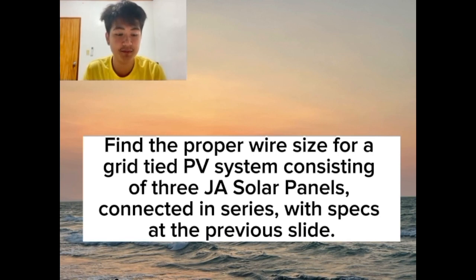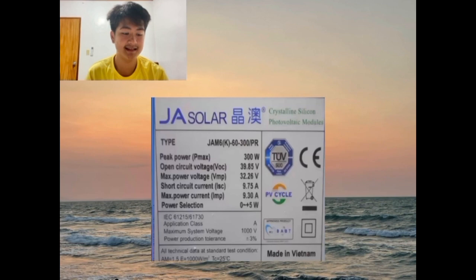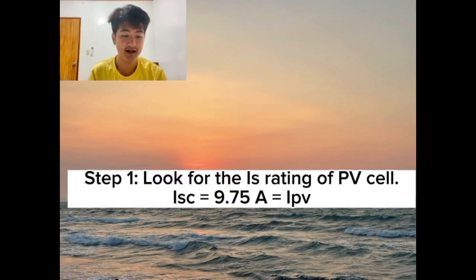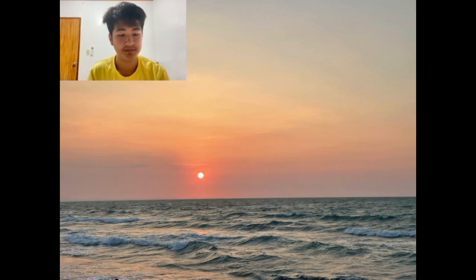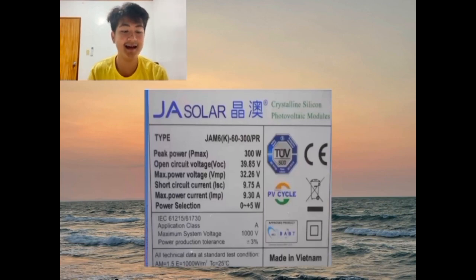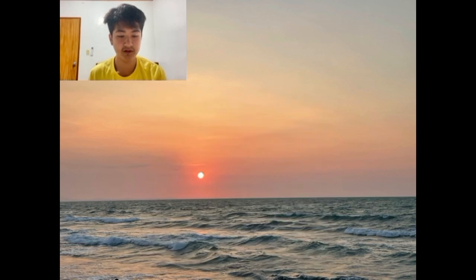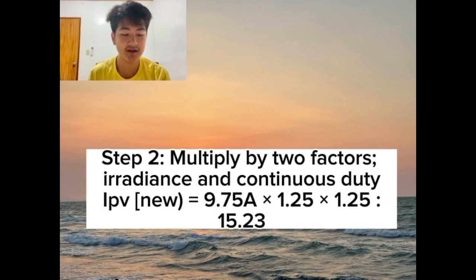Find the proper wire size for a grid-tied PV system consisting of 3 solar panels connected in series, with specs at the previous slide. So, ang magiging example natin is the solar panel. Step 1, look for the ISC rating of the PV cell. Makikita natin dito na ang ISC rating niya is 9.75 ampere. Next, step 2. Multiply by 2 factors, irradiance and continuous duty. Dito naman kailangan natin siyang i-multiply ng 2 beses sa 1.25. So, 9.75 ampere times 1.25 times 1.25 is equal to 15.23.